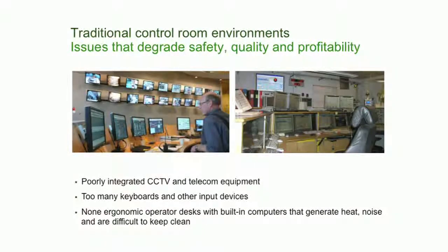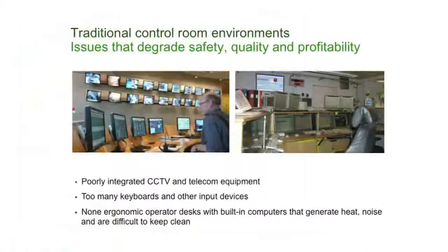Too many keyboards. I don't know if you can see that right picture. You can count to 11, 12 keyboards in 3 different levels. There's absolutely no way you can deal with that in a critical situation. It's quite funny. You ask the operator, how does this work for you? And of course, he's been there since they started, 15 years. So he said, no, I have no problem. The problem occurs when he is retiring.